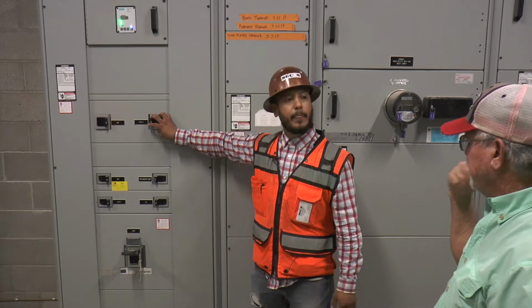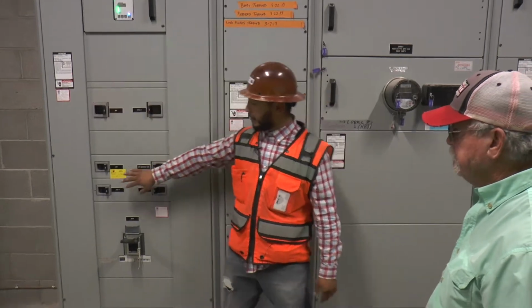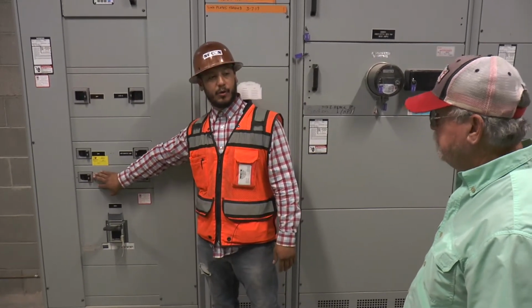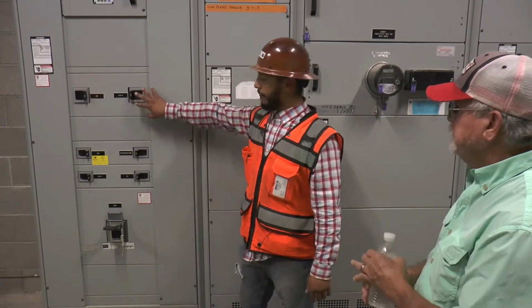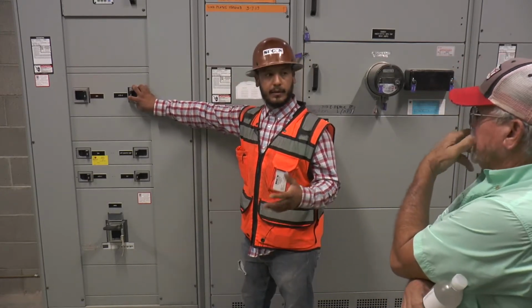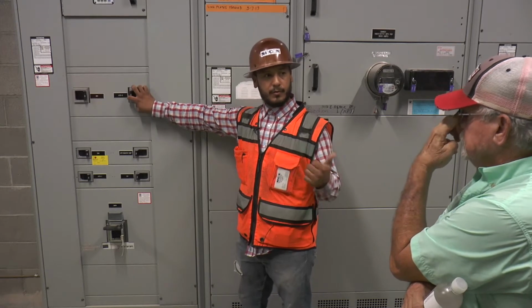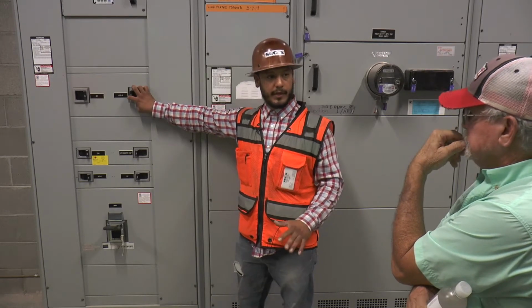So that's the one you shut down and it kicked the generator? Right. Actually, the one we shut down was ATS1, which I was going to get to next. This is 480 equipment that's handling the back of house elevators, which is 480, supply fans 480.